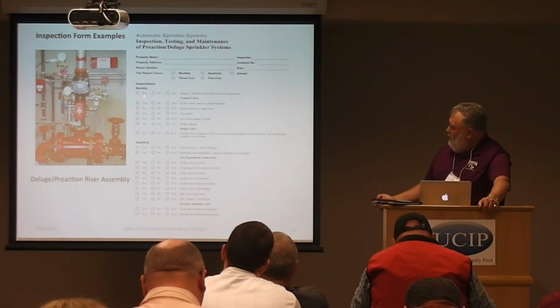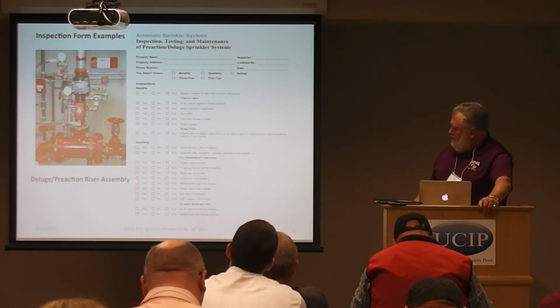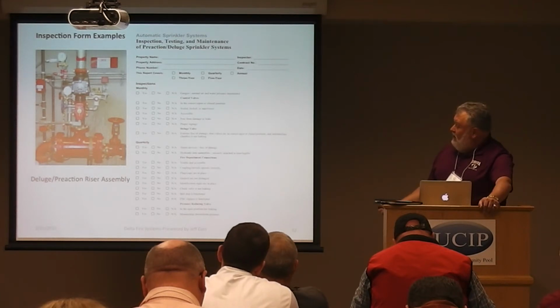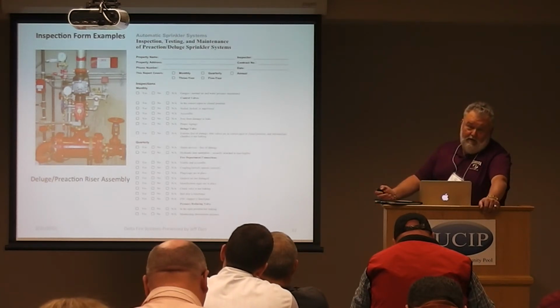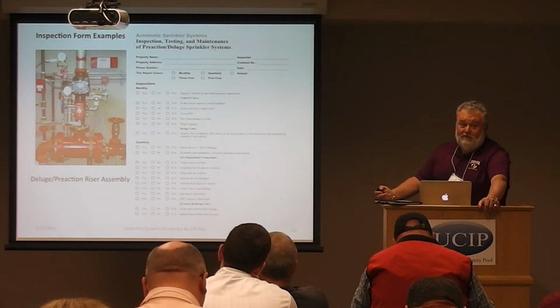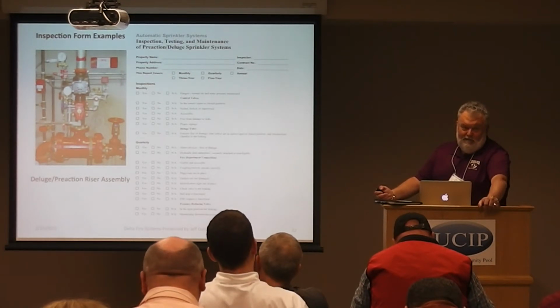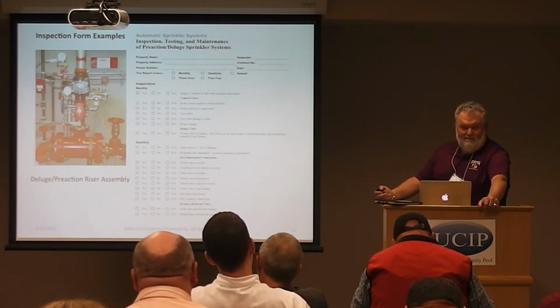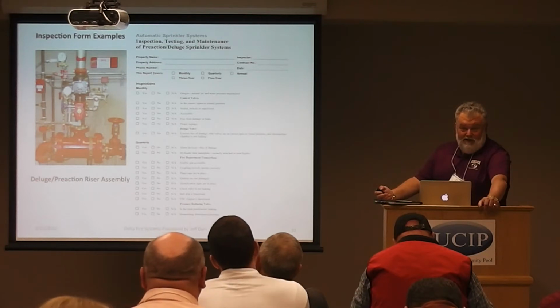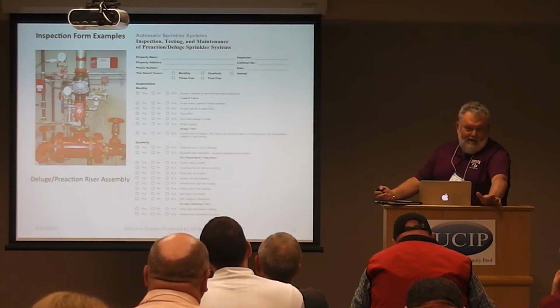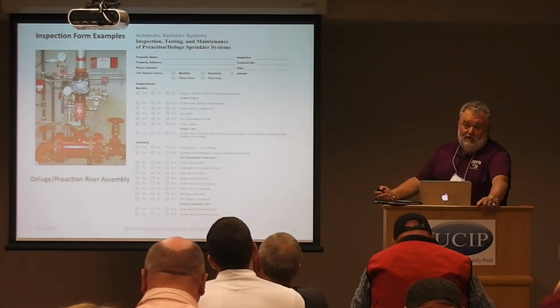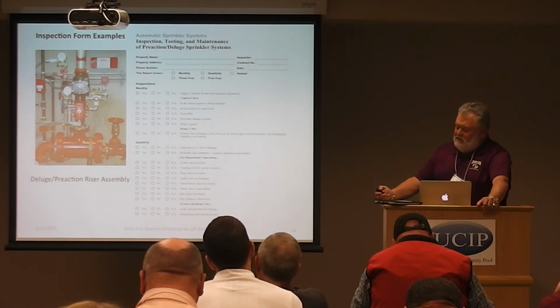But again, we're back to the monthly, quarterly inspections on these. On these type of systems, you also have the requirement for the NFPA 72, the alarm detection part of that. These two systems have a separate detection part. The old, what I call the Hollywood movies where all the heads go off at once, that's a deluge system. You'll see that mainly in high-risk areas, aircraft hangars, around transformers and power plants and so forth.